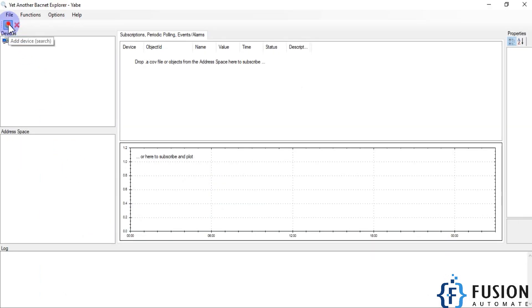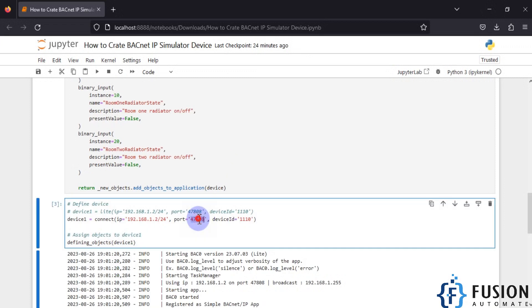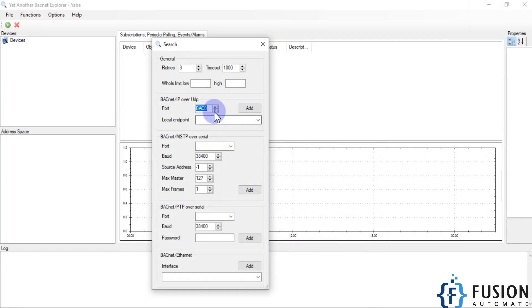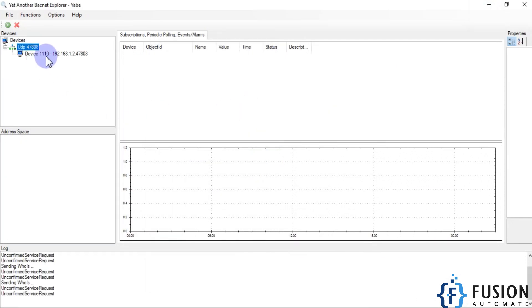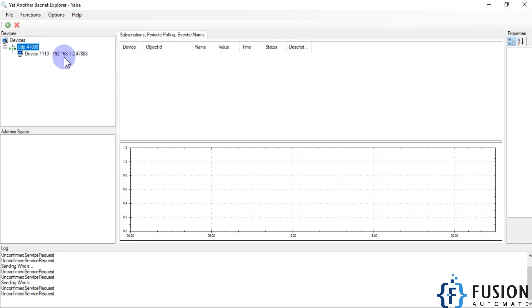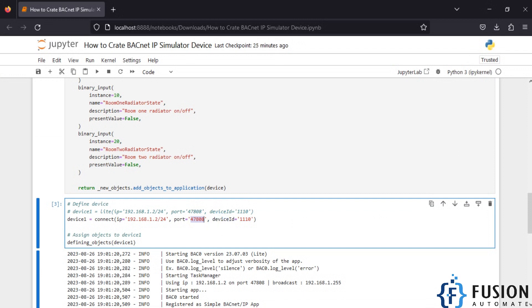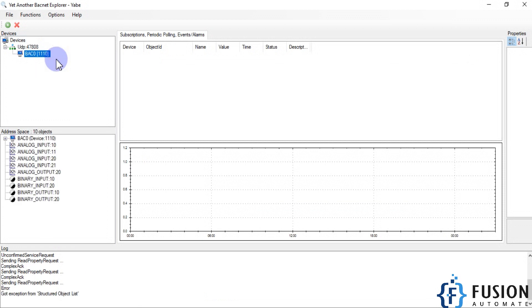Our device is up and running. Now, before simulation, we want to see this device. We open the BACnet client software YABE and click 'Add Device'. You can see bac0 — port number 47808 is equal to bac0. Clicking Add, you can see device 1110 is available. We kept our device ID as 1110, which is why this device appears here, showing IP 192.168.1.2 and port 47808.